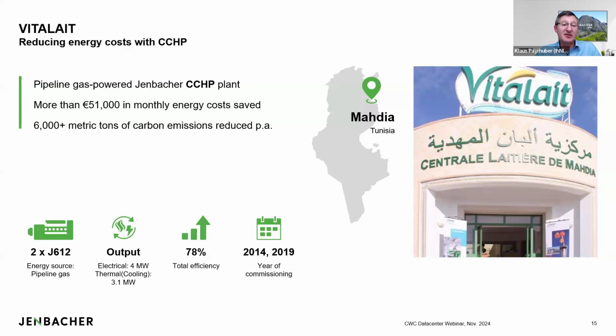This is a typical CCHP application in a hot country, in Tunisia. The CCHP is producing power with about a 4 megawatt engine in total, and cooling of about 3 megawatts. Due to the high efficiency of close to 80% total efficiency, a high fuel utilization rate, the customer is saving a lot of fuel and money, around 50,000 euros a month. In addition, because this engine is still running on natural gas, they're saving a lot of carbon dioxide.